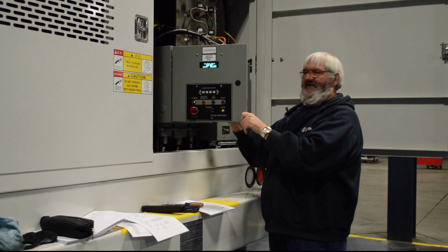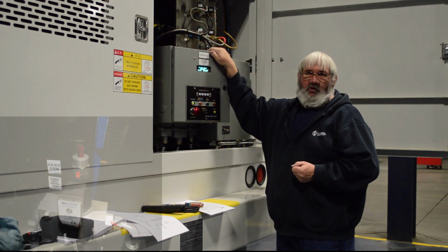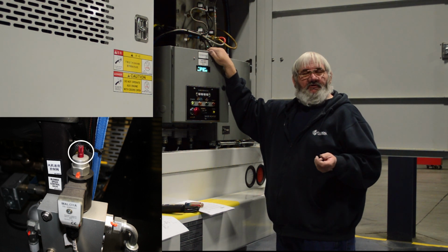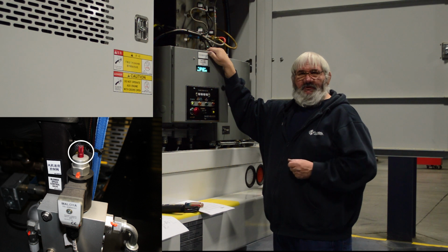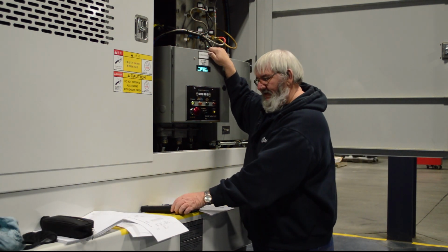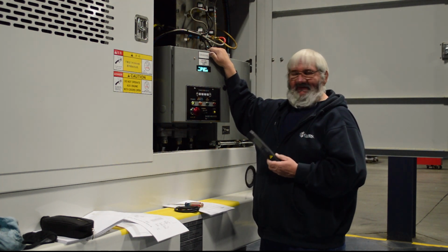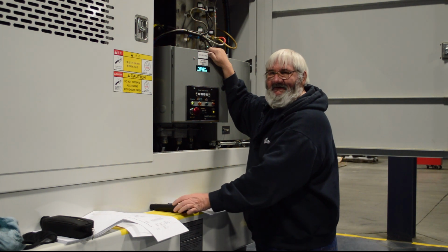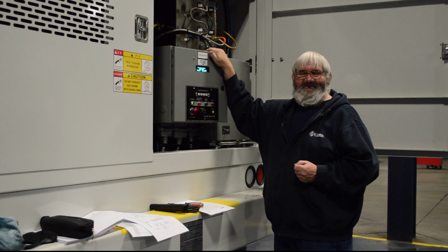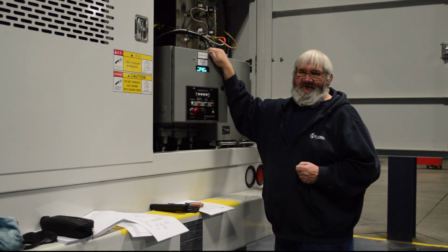Now, from here, you could go back to your blower control valve and use your manual override on your blower control valve to spool your blowers up. As you're doing that, you could use your phototach to measure the RPM. Keep in mind that 4095 signal should be 5,000 RPM. Zero signal should be 300 to 500 RPM.